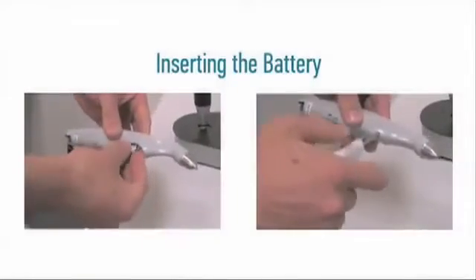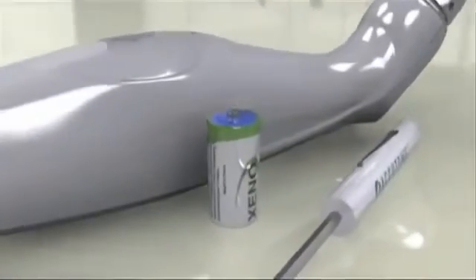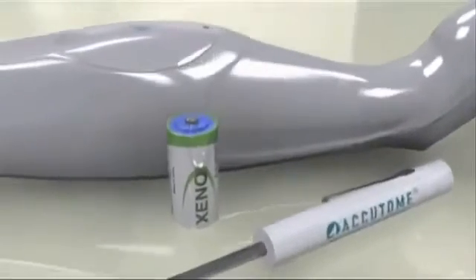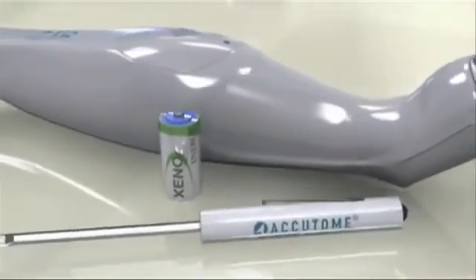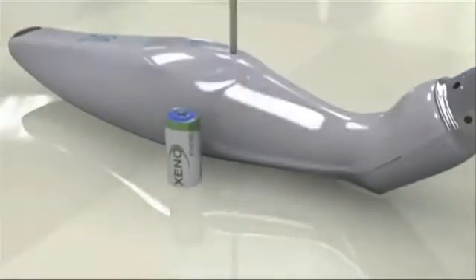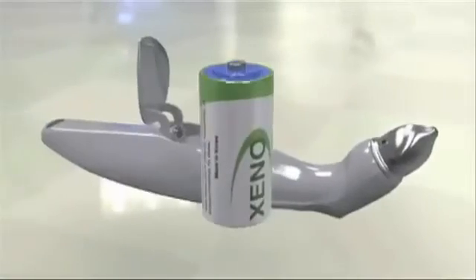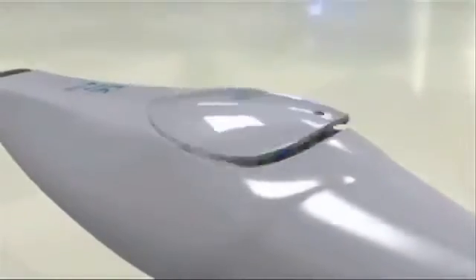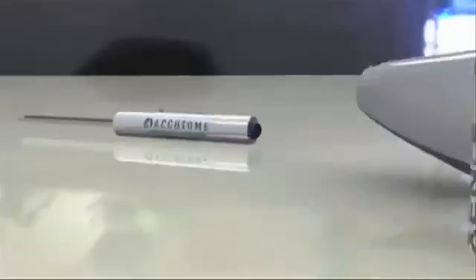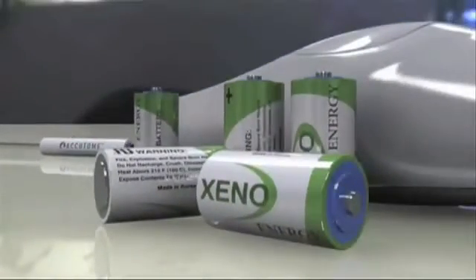Inserting the battery. When you first unpack your AccuPen Vet, the 3.6-volt lithium battery must be placed inside the unit. Take the screwdriver to open the casing and place the battery inside the unit. Use a screwdriver to tighten the compartment shut. Be sure not to over-tighten the screw. Batteries typically last 15,000 measurements or 1 year and can be purchased from your AccuPen Vet representative.